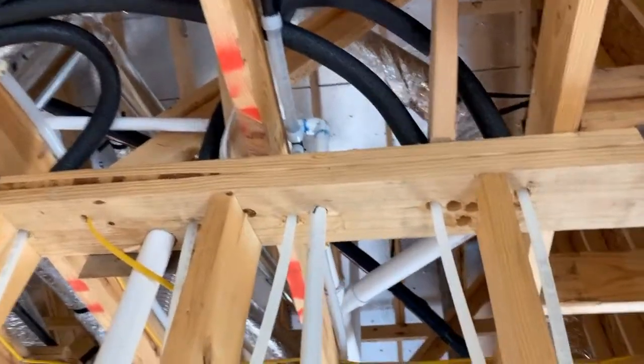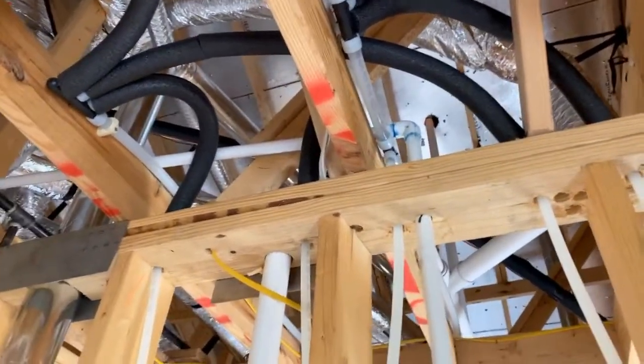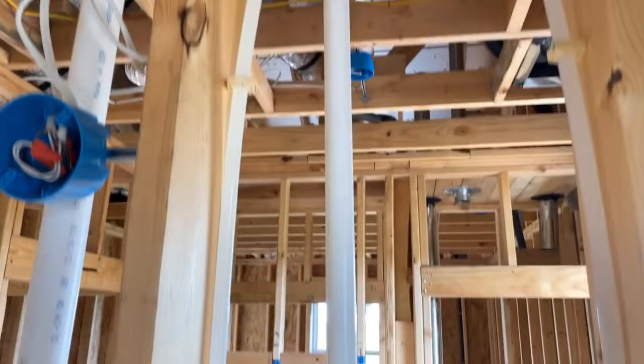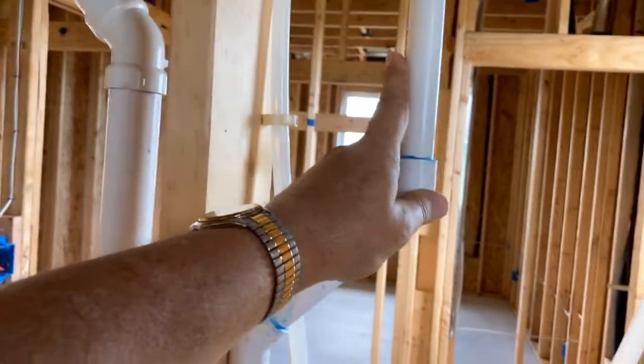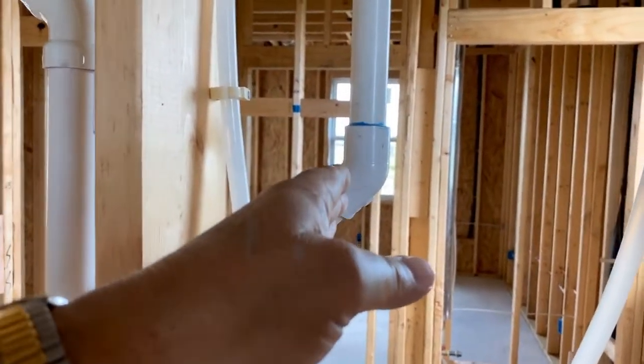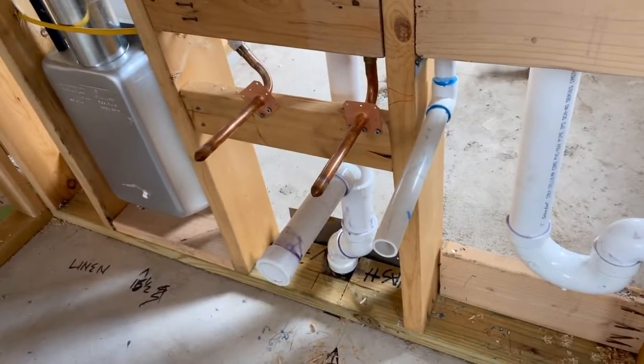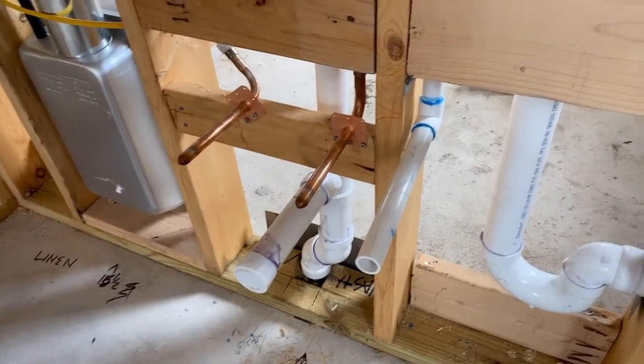One thing we don't get to see during or after construction is the primary AC drain. We saw it up at the AC unit and it runs somewhere. Well, it comes over to a top plate, comes through the top plate, and comes down. You'll notice here there's an offset. The water comes down from up above in the attic — rather than going straight down into a dead end and dripping and making noise at night, it hits the offset and trickles down the walls of the pipe. Then it'll go down to the drain, which will eventually tie into the drain of the sink.